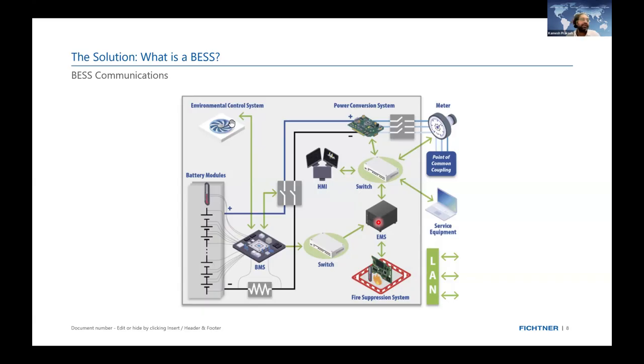As the grid, if I want to use the BESS for a certain application, I need to respect the limitations of the battery pack, such as SOC (state of charge), SOH (state of health), and DOD (depth of discharge). Unlike everyday life, where even if your phone reaches 15% you know you should charge it, but instead use it until 10% or 4% before plugging it in—which spoils the battery over time—we don't allow that to happen in a grid-scale storage system. We need to respect the boundary conditions of the battery, which gives indications through communications.